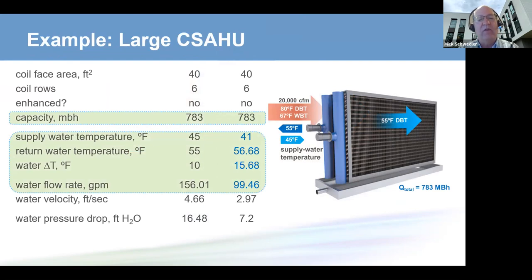Well, in this case, when we give this coil colder water, say 41 degree water, the water returns at about 57 degrees. So we went from a 10 degree delta T to approximately a 16 degree delta T. We had the same leaving air conditions, the same capacity. Therefore, nothing happens with fan airflow. So if we have a system where we've maximized the flow rate in our pipes, some people think, well, I can't get any more tons out of it. We can, by selecting chillers, or having the present chillers, if they can, make colder water.